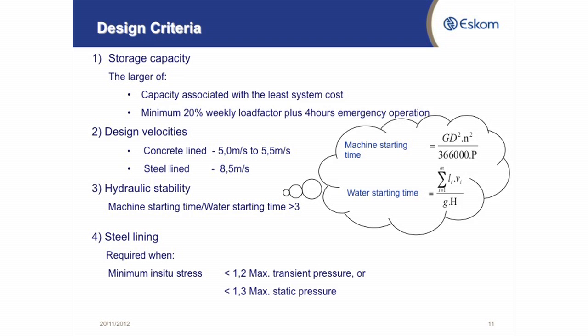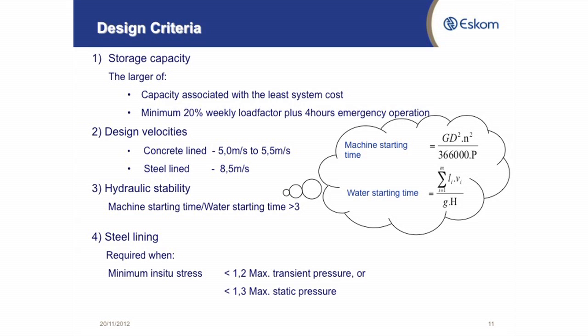But we also said we want to use this pump storage at least at a 20% load factor in the week. And we always want to retain 4 hours in the upper dam for emergency conditions. So these are the 2 criteria we used, and from that it resulted in a 16-hour upper dam and lower dam. The waterways have been designed for 5 meter per second velocity and sized. At overload we accept 5.5 meters per second, steel liner 8.5.